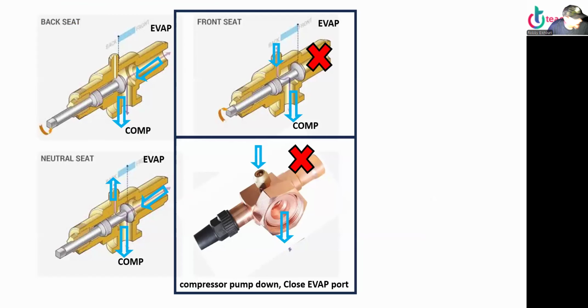So let's talk about the valves. We have back seat, front seat, mid seat, neutral seat. So back seat, that's how we are at home watching a movie, a normal operation. It's open to the evaporator, open to the compressor, and closed to the service port, and a cap should be there.